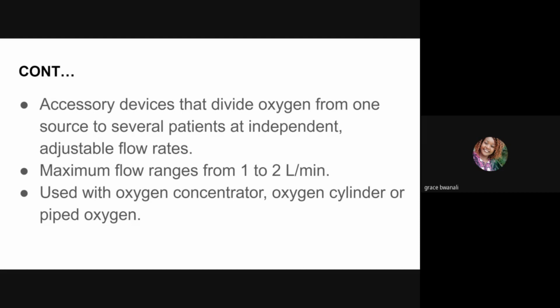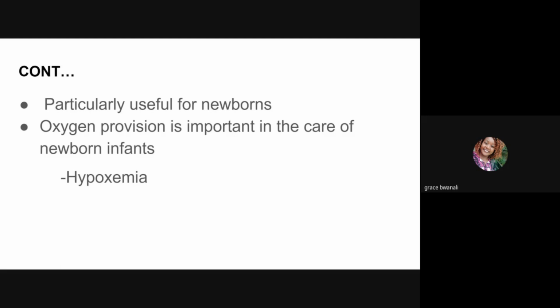Flow splitters are accessory devices that divide oxygen from one source to several patients at independent adjustable flow rates, depending on the required dosage for an individual patient. Depending on the model of the splitter, their maximum flow ranges from 1 to 2 liters per minute on one output. Note that flow splitters can be used with oxygen concentrators, oxygen cylinders, or piped oxygen. They may also be combined with CPAP if the oxygen source and the splitter flow meter have the capacity for the flow rates required. In Malawi and many hospitals, flow splitters are particularly being used for newborns who only require small doses of oxygen.